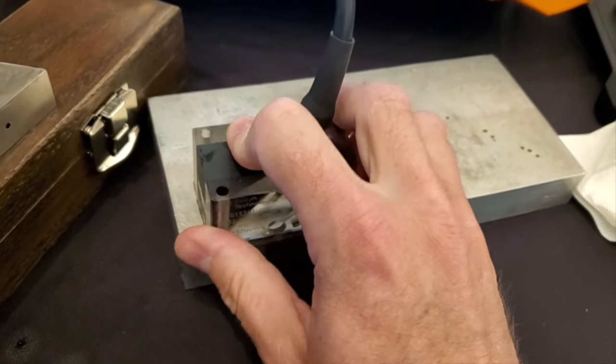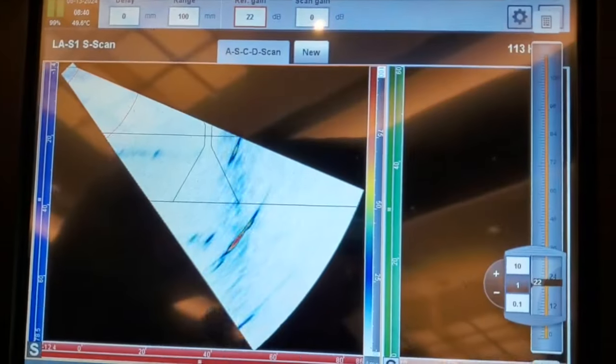What's That Weird Thing, Part 2, from the NDT in Canada 2024 Ottawa show. PH Tool made a block with angled ends. With regular calibration blocks with a flat end, when you have a hole or reference reflector, you're going to get interference from these corners when you're trying to make a TCG.